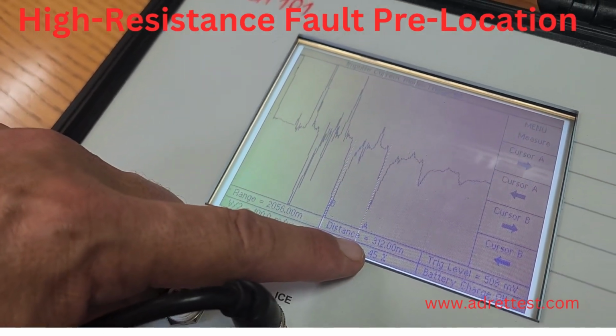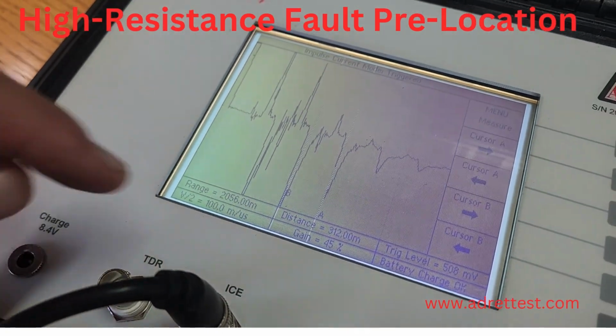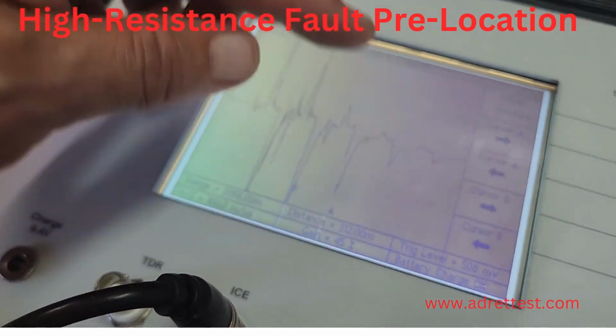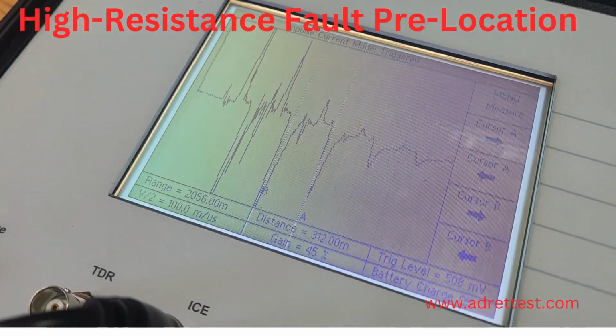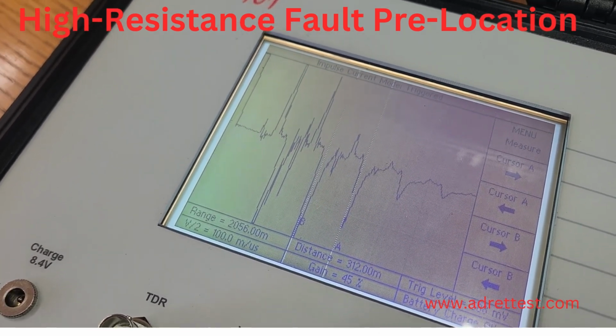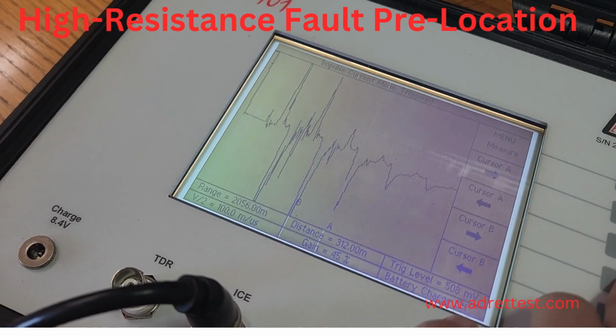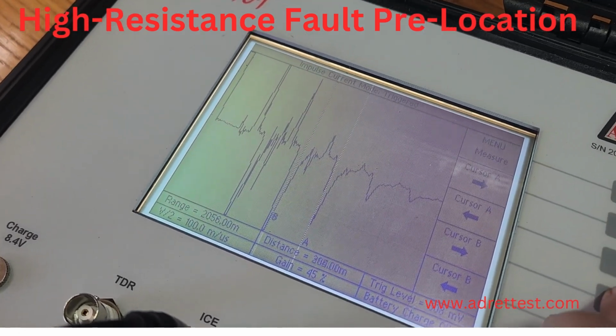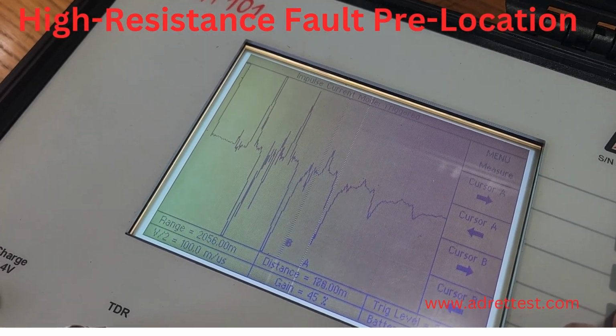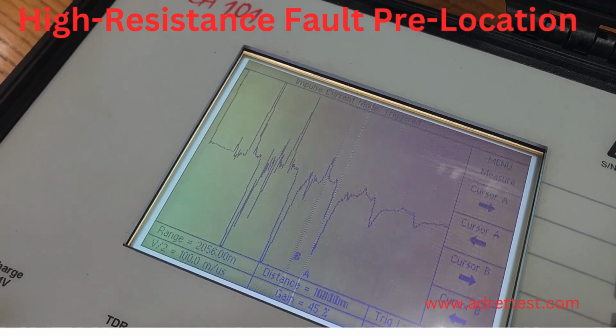Rule of thumb is you always go from where you are to the distance that it gives you, or you start at that distance coming back on the cable. In that way you will never overshoot, but you'll always walk over your fault. Just to demonstrate, if I move my cursor B to my next peak, it will give me that same distance, just to show you guys that that is the distance to the fault.